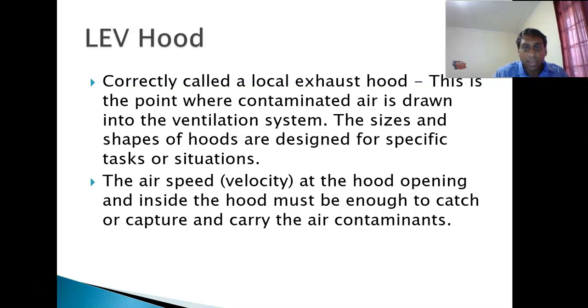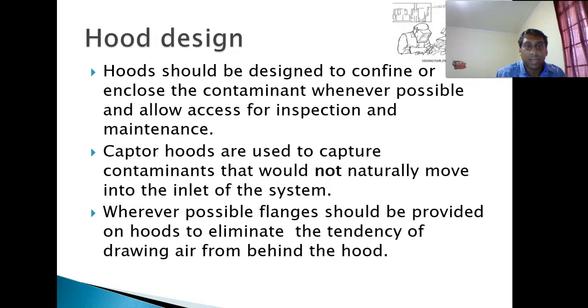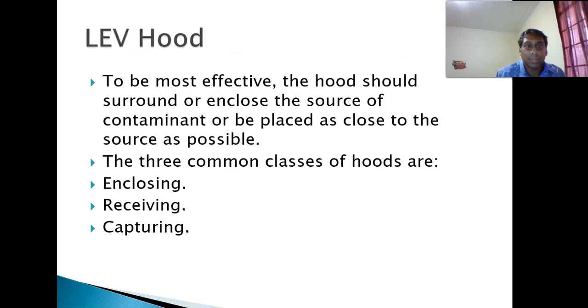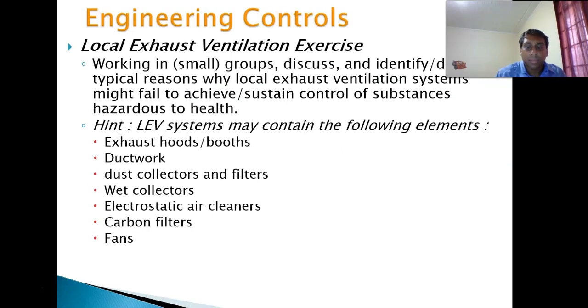So there is actually something called the capture velocity, and what that really is, simply saying, is that the speed of air is great enough to suck those contaminants in, right? But some of those terms, as you go through your handout, you have to use the proper terms. This capture velocity must be enough to catch or capture and carry the contaminants in. There's actually something called the transport velocity as well, which is, once inside the hood, it will be able to carry the contaminants into the hood. Right, I think I'm right there.